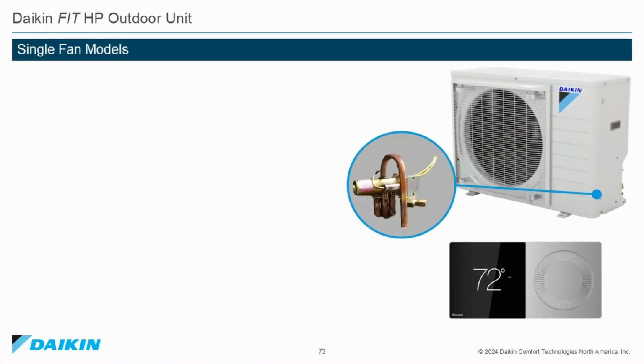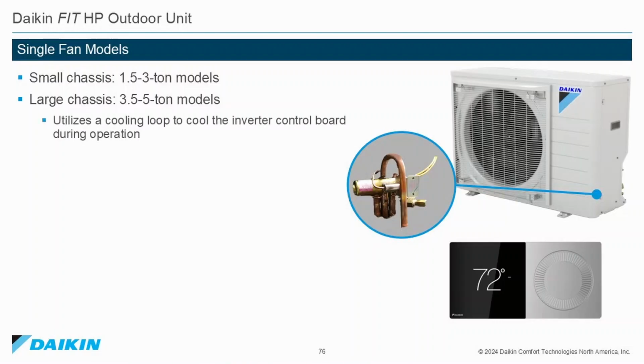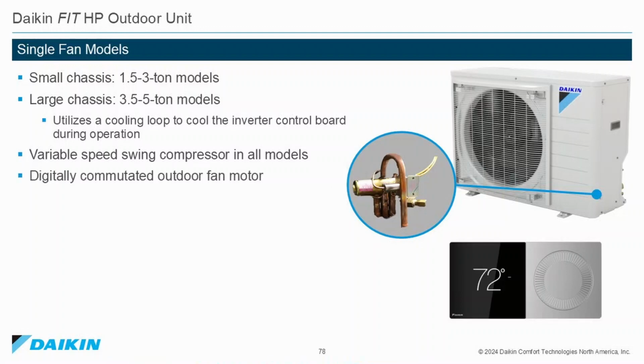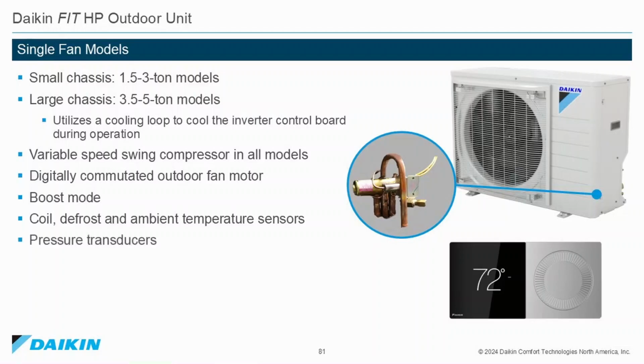The Daikin Fit heat pump outdoor units. Single fan models. Small chassis, 1.5 to 3 tons. Large chassis, 3.5 to 5 tons. Utilizes a DX cooling loop to cool the inverter control board during operation. Variable speed swing compressor in all models. Digitally commutated outdoor fan motor. Boost mode. Coil, defrost, and ambient temperature sensors. Pressure transducers. And utilizes Daikin approved communicating thermostats.